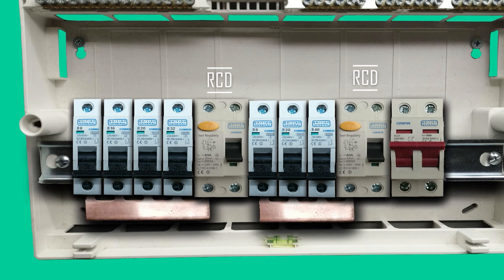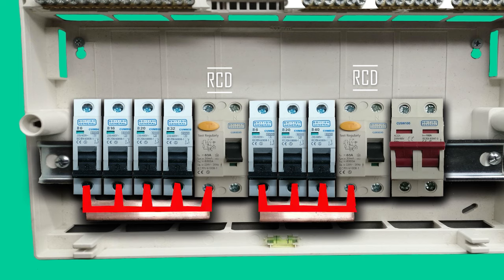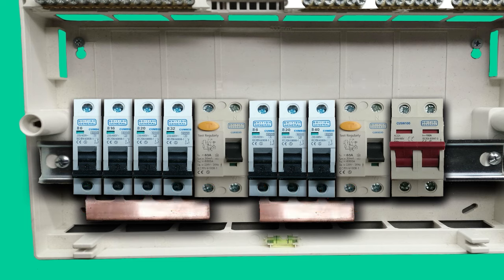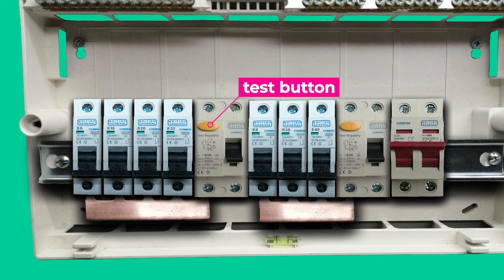The RCD will detect this imbalance and disconnect the whole circuit. The RCD cannot always prevent an electric shock, but can minimize the risk of serious harm to a body. The RCD will disconnect not only the circuit with the fault, but all the circuits that are connected to it. Each RCD has a test button. This is the yellow button on top. To test it, you need to press it and then the RCD should trip.